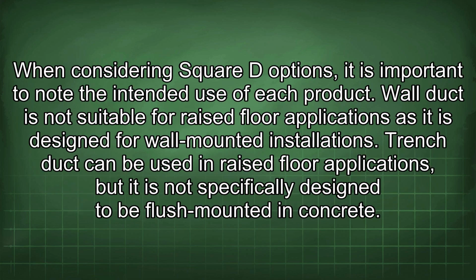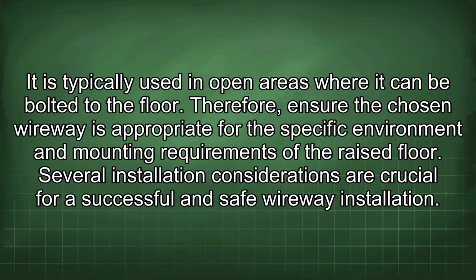When considering Square D options, it is important to note the intended use of each product. Wall duct is not suitable for raised floor applications as it is designed for wall-mounted installations. Trench duct can be used in raised floor applications, but it is not specifically designed to be flush-mounted in concrete. It is typically used in open areas where it can be bolted to the floor. Therefore, ensure the chosen wireway is appropriate for the specific environment and mounting requirements of the raised floor.